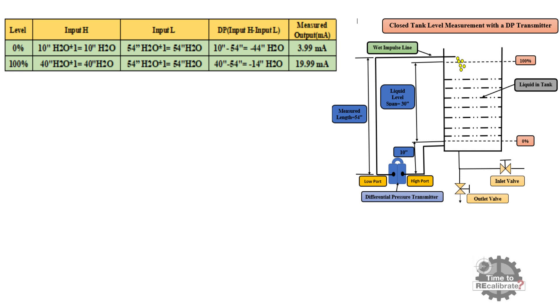Now let's understand the calculation at 100% level. At 100% level, the DP transmitter high side has 40 inches H2O pressure, multiplied by the specific gravity of water. Here, 40 inches is the total distance from the transmitter to the 100% line. So the DP transmitter high input side has 40 inches H2O pressure at 100% level. Similarly, at 100% level, the transmitter low side has 54 inches H2O pressure, multiplied by the specific gravity of water which is 1. So the DP transmitter low side has 54 inches H2O pressure at 100% level. Differential pressure is 40 minus 54, equal to minus 14. At 100% level, differential pressure is minus 14 inches H2O.